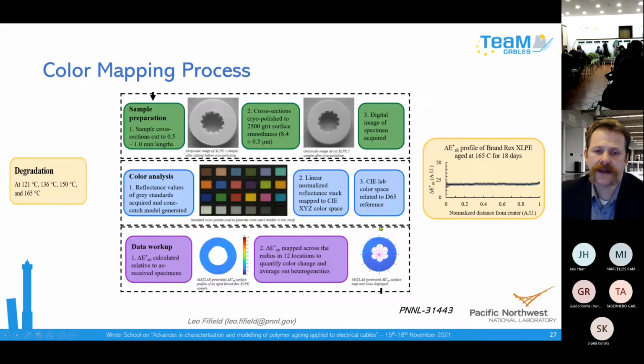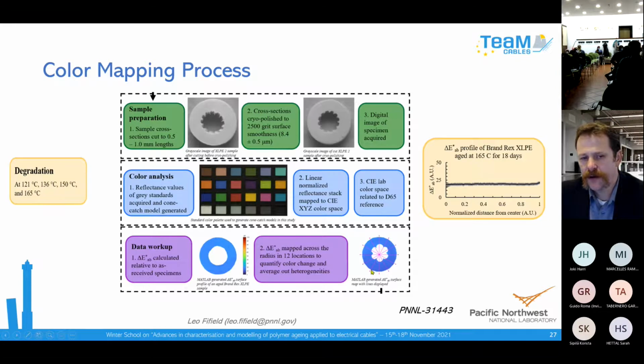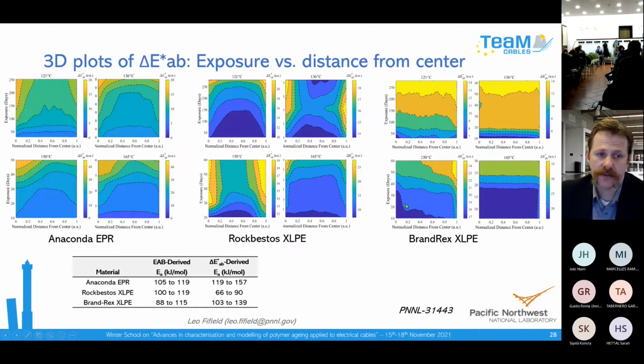Here is the new technique we developed using color change on these similar samples. As cross sections are polished, we're able to image the whole slice of the cable insulation all at once, and then quantify the color change locally with just optical microscope resolution. And then we can normalize and track through the thickness of that insulation to look at the behavior across the thickness. So that's how we pursued it.